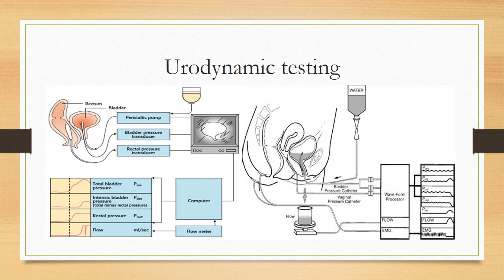So here again, peristaltic pump for filling the bladder, bladder pressure transducer, rectal pressure for abdominal pressure, then total bladder pressure is measured. Intrinsic bladder pressure is gained by deducting abdominal pressure from the bladder pressure. This rectal pressure, P rectal, measures the abdominal pressure, then flow rate is measured, and all recordings are calculated in a computer. Here the patient lies in this way, and here this is the screen.